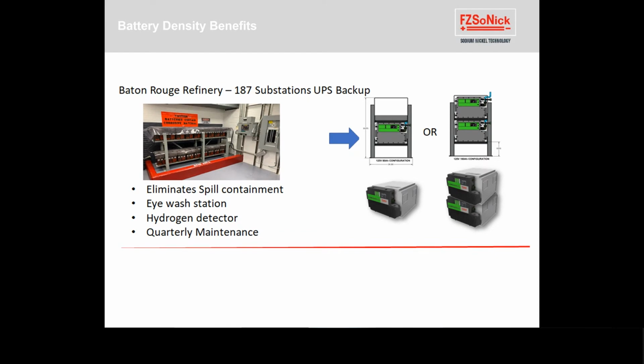We can generally do that with one of our modules, about 24 inches by 24 inches and approximately 12 or 13 inches tall. With 160 amp hours, we can replace just about most of the smaller switchgear strings that are produced, with a zero maintenance battery that lets you eliminate spill containment, eye wash, hydrogen detection, and of course quarterly maintenance or watering.